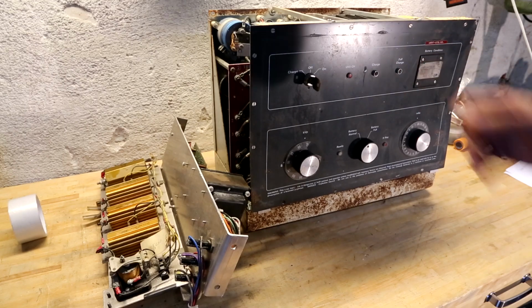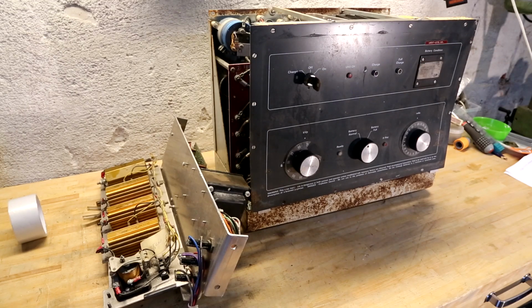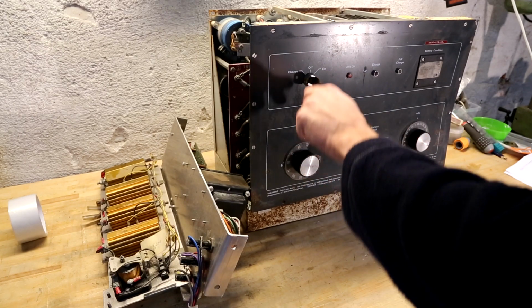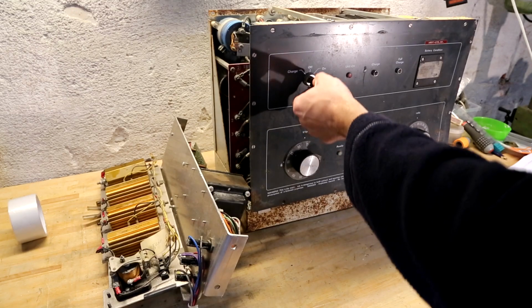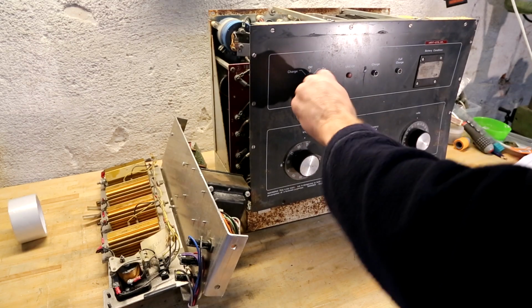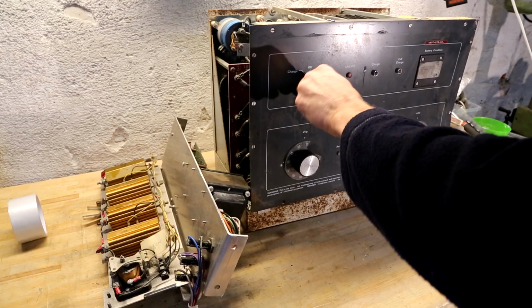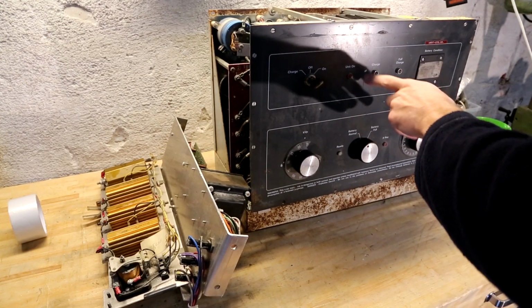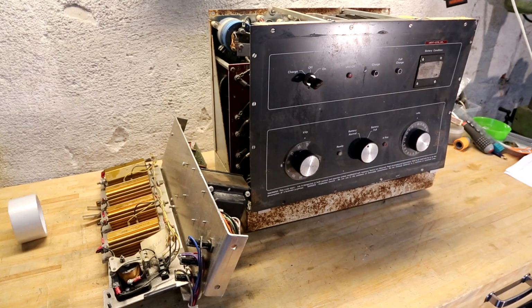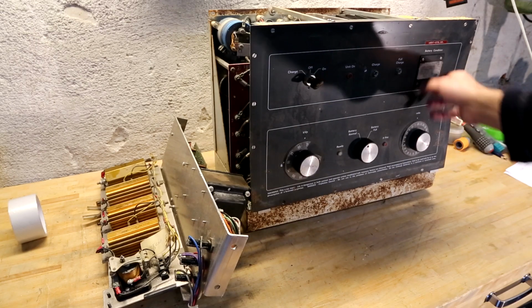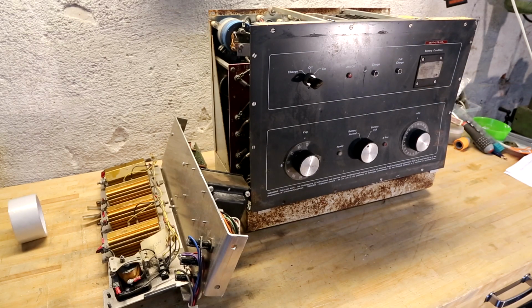It says here weight 370 kilograms, so that's the weight of the whole unit. So that's a good reason why it had some front bumpers and deadman switches. You didn't want 370 kilos going amok in a hospital. Now up here there's a key switch for on-off and for charge. There's an indicator for unit on. If it's charging, it's fully charged. And then the battery condition meter is missing because these units have been rebuilt for main supply instead of battery supply.